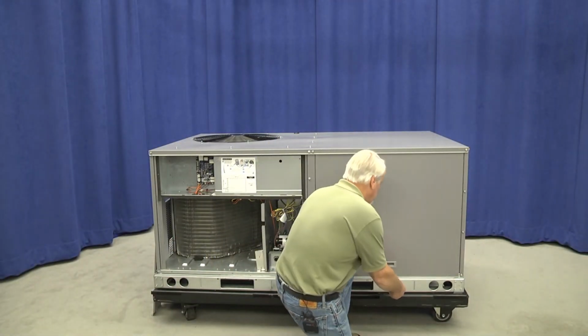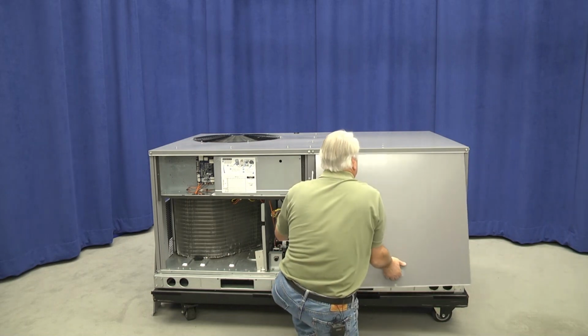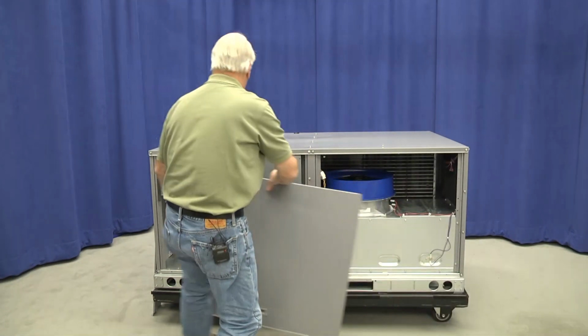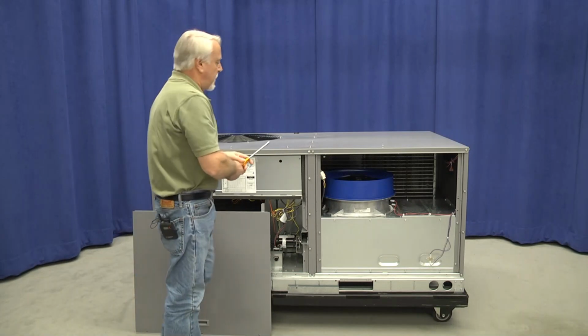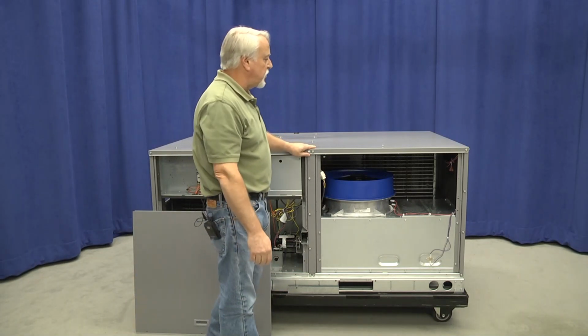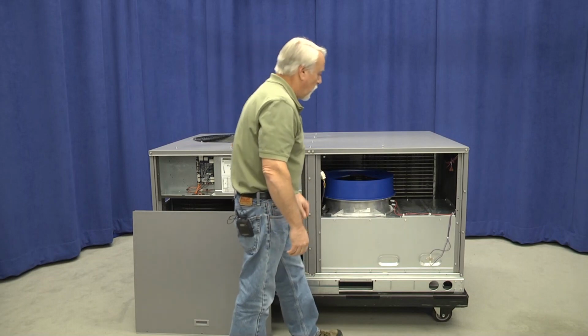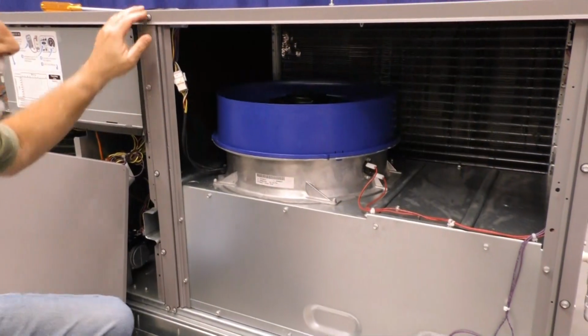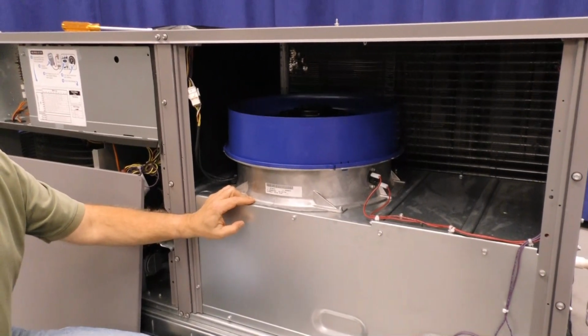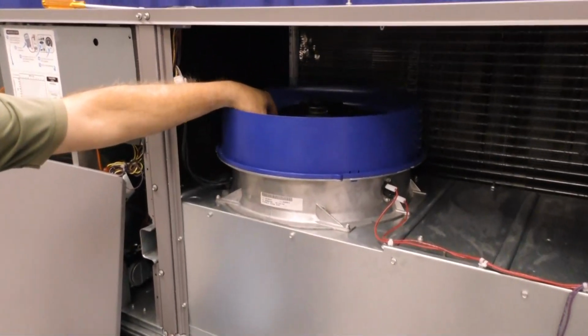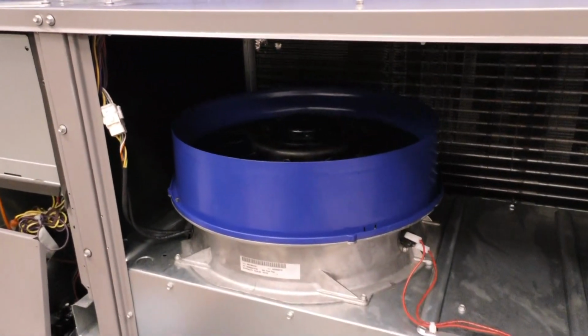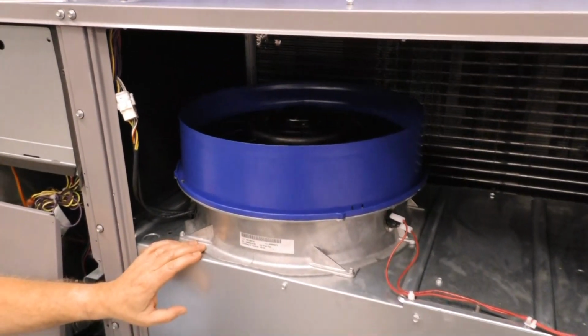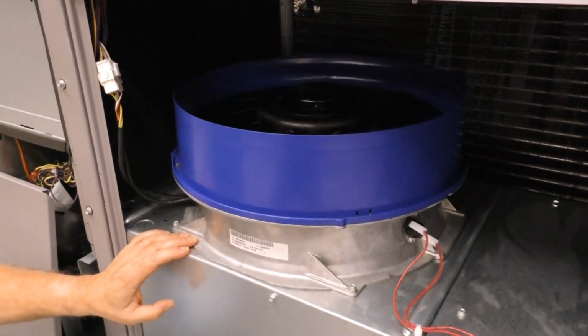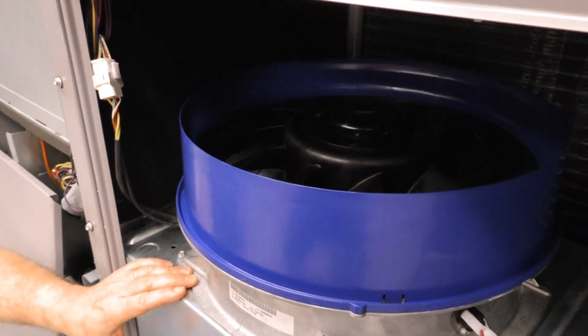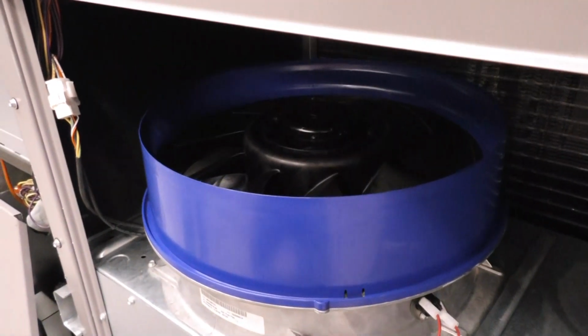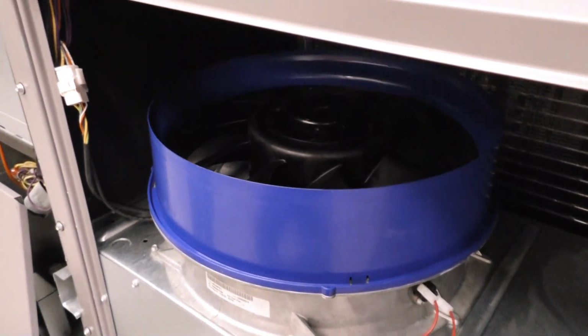Moving to the indoor fan panel, there is a significant difference compared to the old units or the current design. Previous to this, we had a forward curve fan. Now we are moving over to a vane axial fan. It's a composite fan, not a metal fan. It's direct drive, and it's controlled by an ECM motor. The use of this particular design with these ECM motors has eliminated the requirement for a variable frequency drive on some models.